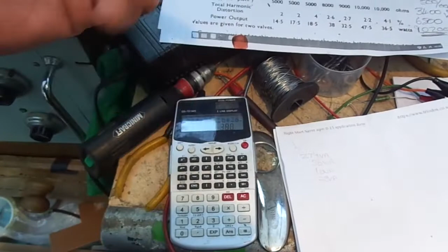Why add some on? You've got the core losses and the winding losses. So you've probably got something like 2% core loss and 5% winding losses. The winding loss is basically the copper acting as a resistance. There's a lot of copper on a transformer this size, and some of that is going to get lost as heat, because there's going to be some resistance. When you've got resistance, you get heat. So I add, like I say, 10%.